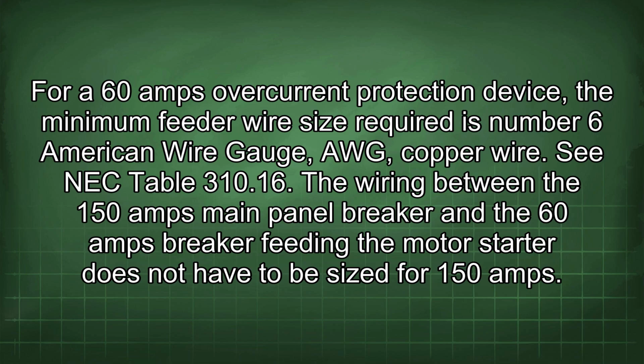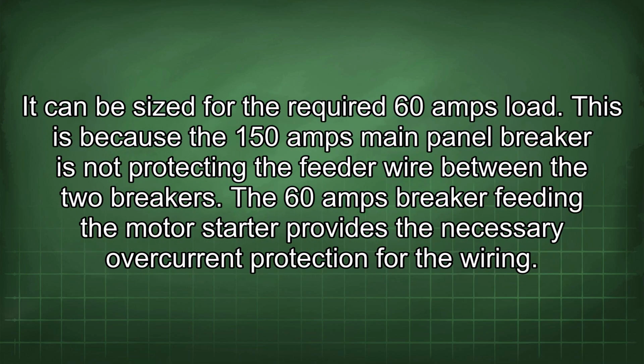The wiring between the 150 amp main panel breaker and the 60 amp breaker feeding the motor starter does not have to be sized for 150 amps. It can be sized for the required 60 amp load. This is because the 150 amp main panel breaker is not protecting the feeder wire between the two breakers. The 60 amp breaker feeding the motor starter provides the necessary overcurrent protection for the wiring.